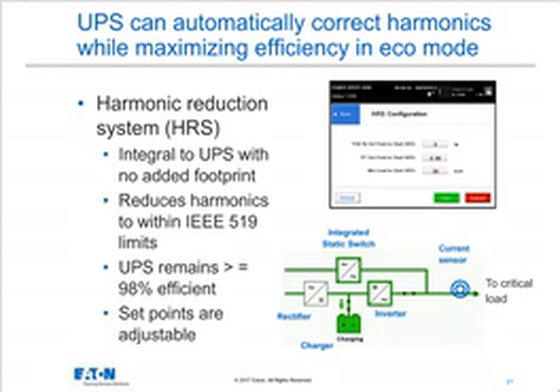So the next slide should have a heading that says the UPS can automatically correct harmonics while maximizing efficiency in eco mode. If you're familiar with modern UPSs, most of them do offer what we call an eco mode or an energy saver system. Now, in this case, the UPS is frequently operating with its static switch conducting, and the power comes from the utility straight through the UPS and directly to the critical load that we're supporting, and as a result, there's very low losses and very high efficiency in the UPS. So that's very beneficial and very desirable.